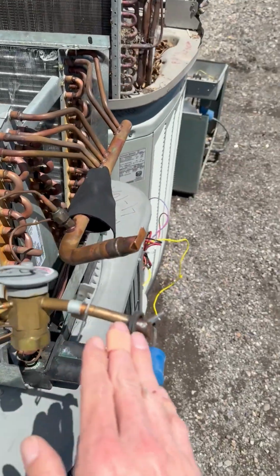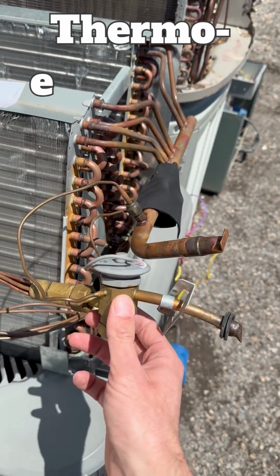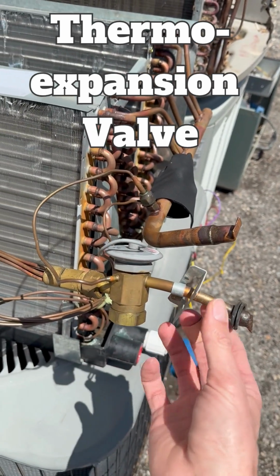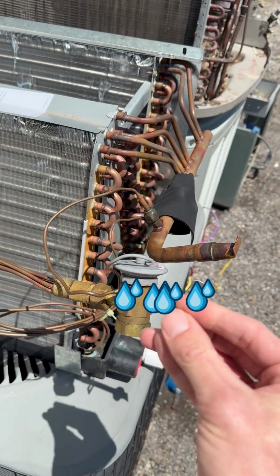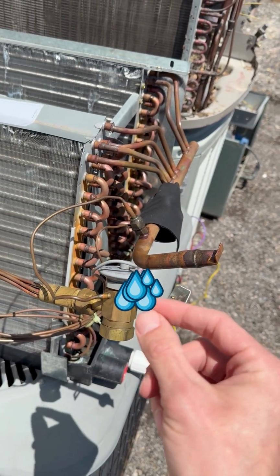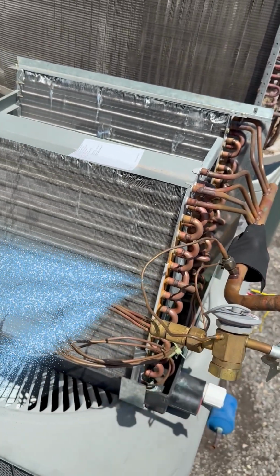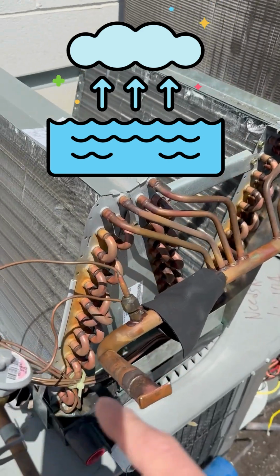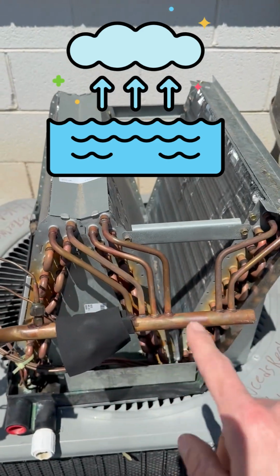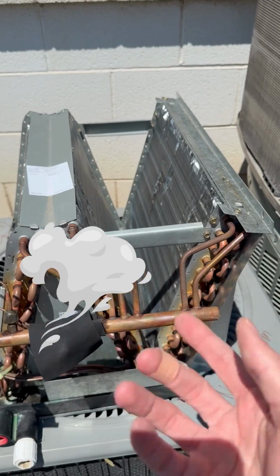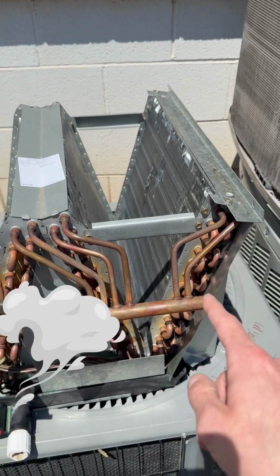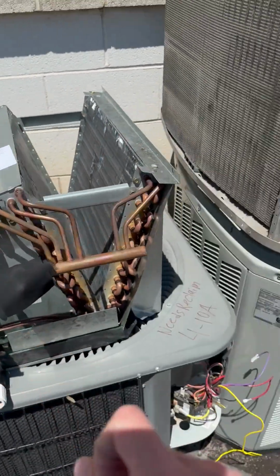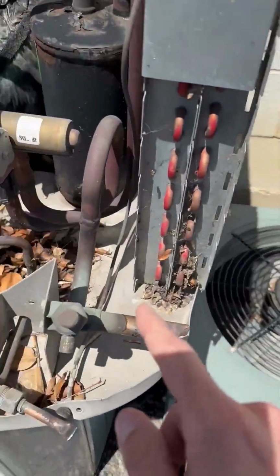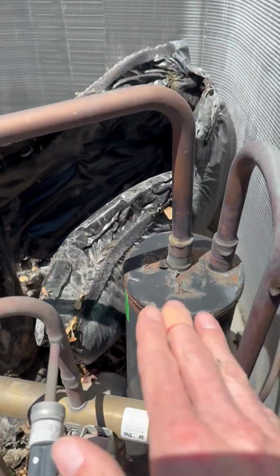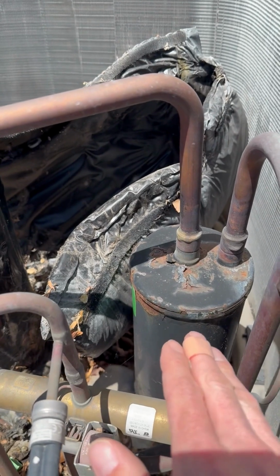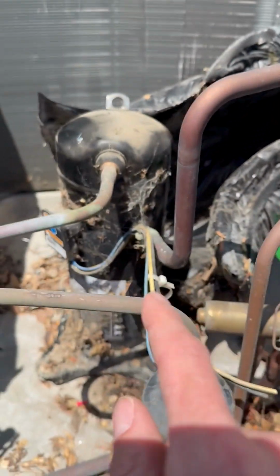It's going to go through this TXV or some sort of orifice. What this does is it takes that high pressure liquid into a very low pressure state. That low pressure state then evaporates inside of our evaporator coil, absorbing heat, and turns back into a vapor. That vapor is then sucked all the way through our suction line back, in this case through an accumulator, to ensure that only vapor gets to our compressor.